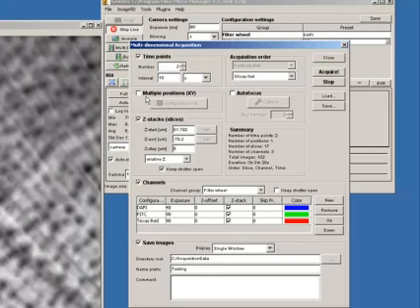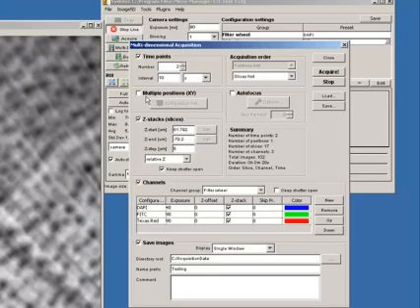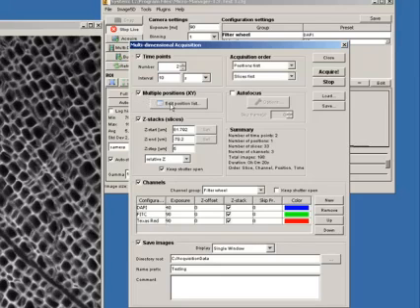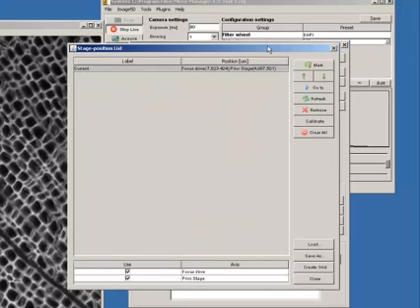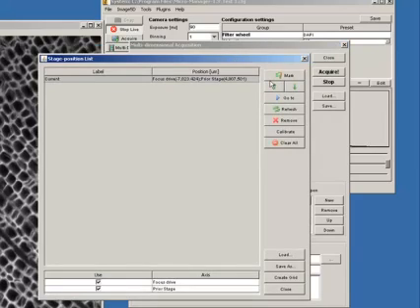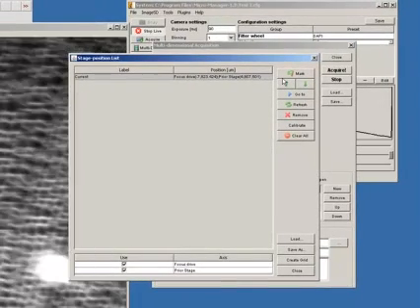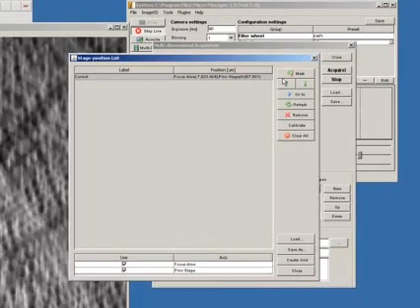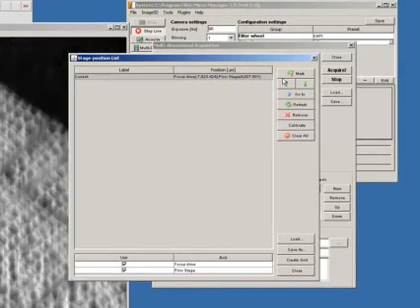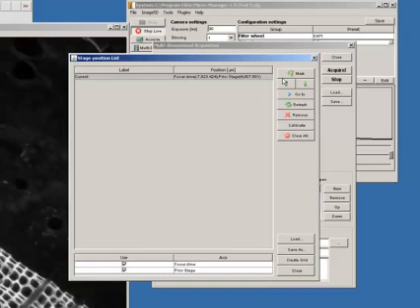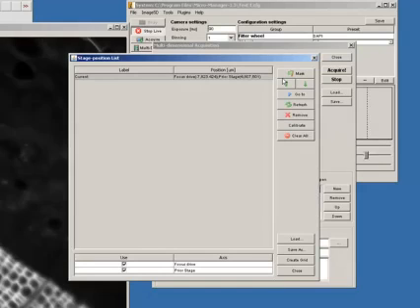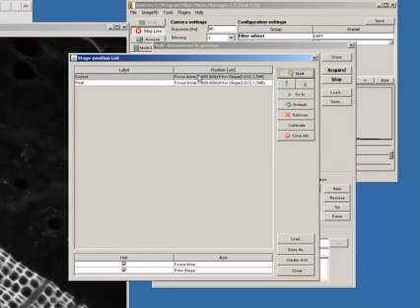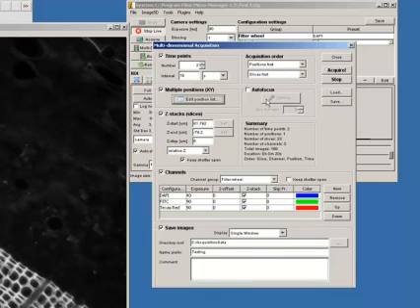And then for multiple positions. Let's just roll us back towards focus a little bit. We can tick the multiple positions dialog box. Edit positions here. And this is where we can add in positions. So, let's move the stage around a little. Somewhere else on the sample. That'll do. And we can adjust the focus as well. And then mark that position. So, now I've got my two positions that I've set in. All of these settings can be saved obviously. Excuse me if I want to revisit and reload this experiment later on. So, let's close that.